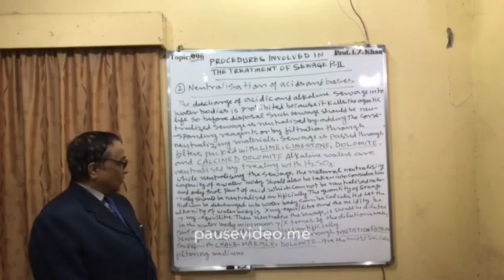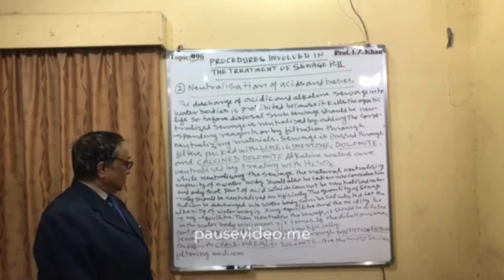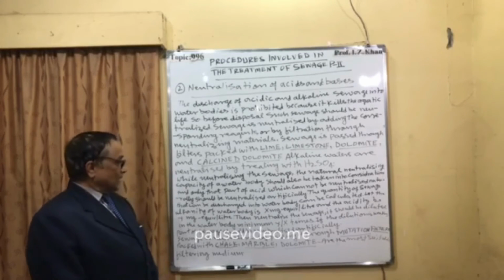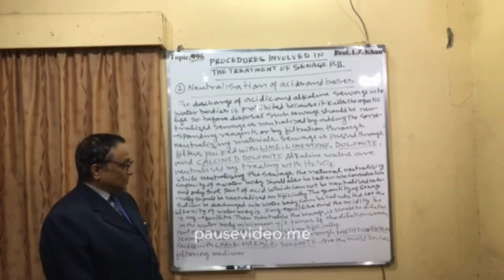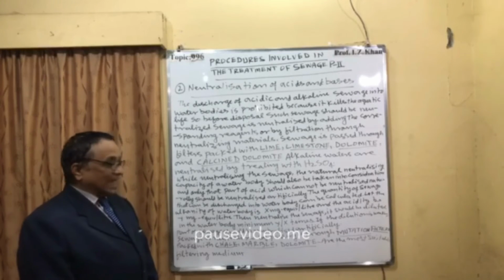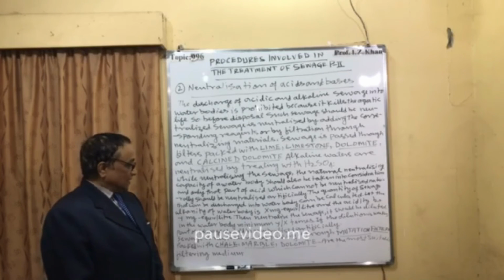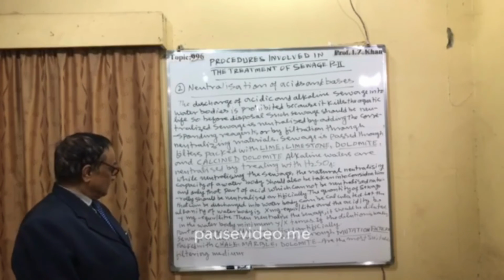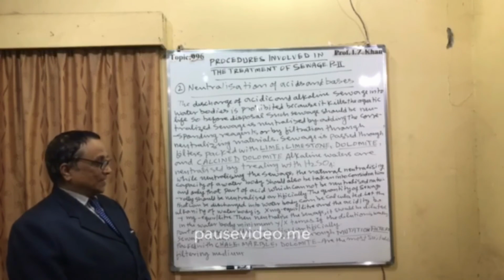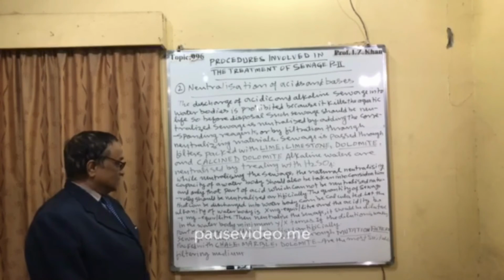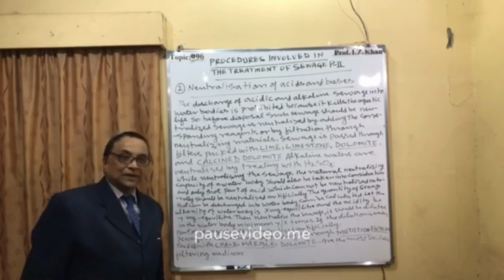Let the alkalinity of water body be X milligram equivalent per liter and the acidity be Y milligram equivalent per liter. Then to neutralize the sewage, it should be diluted in the water body minimum Y by X times. If the dilution is weaker, that part of sewage should be neutralized artificially. Sewage is neutralized by passing it through neutralization filters packed with chalk, marble, dolomite, and these are the most suitable filtering medium.